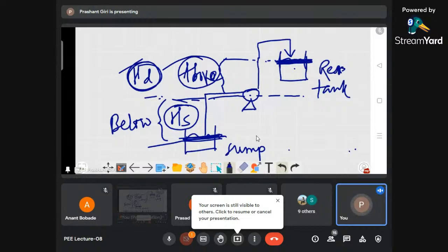आता आपण जर फर्स्ट फ्लोअरला राहत असेल तर विहिरीची पाण्याची लेवल, विहीर ऑलरेडी 100 फूट खोल आहे, तुमच्या फ्लोअरची हाईट ऑन ॲन ॲव्हरेज 12 फूट असते, म्हणजे 100 + 12 इज 112 फीट जर तुमचं फर्स्ट फ्लोअरला तुम्ही पंप ठेवला तर. त्यामुळे आपण काय करतो, बऱ्याचदा विहिरीतच पंप सोडतो. काही सबमर्सिबल असतात, काही नॉन सबमर्सिबल असतात, पण आपण जास्तीत जास्त सक्शन हेड कमी करण्याचा प्रयत्न करतो, कारण त्याला जास्त एनर्जी लागेल. विहीर 100 फूट खोल आहे आणि विहिरीच्या काठावरती जर तुम्ही पंप बसवला तर सक्शन हेड किती मीटरचा झाला, 100 फुटाचा हेड झाला, कारण पाण्याची लेवल खाली आहे. त्या पाण्याच्या लेवल पासून पंपच्या सेंटर पर्यंतचं डिस्टन्स म्हणजे तुमचं सक्शन हेड आहे, तो 100 फुटाचा झाला. तो काय करावा लागेल, तुम्हाला कमी करावा लागेल.